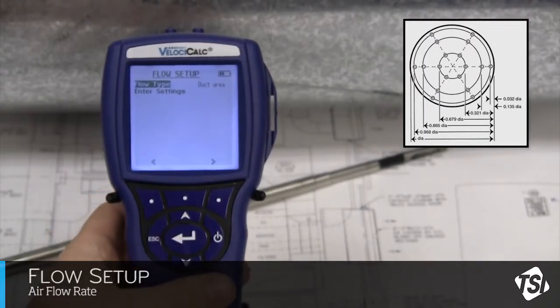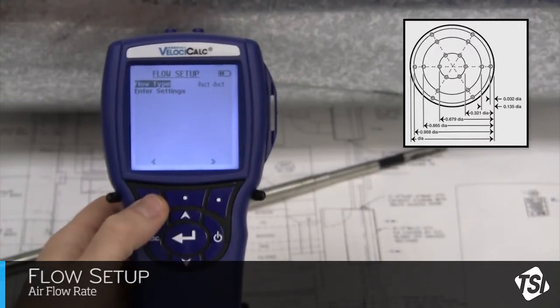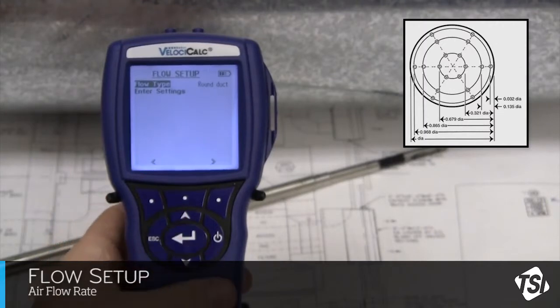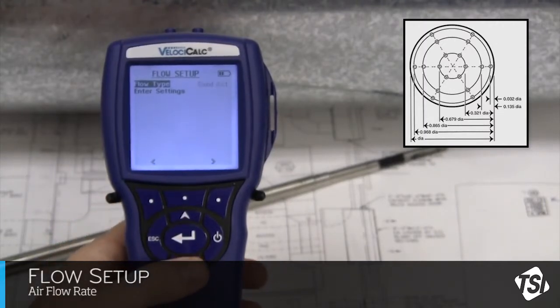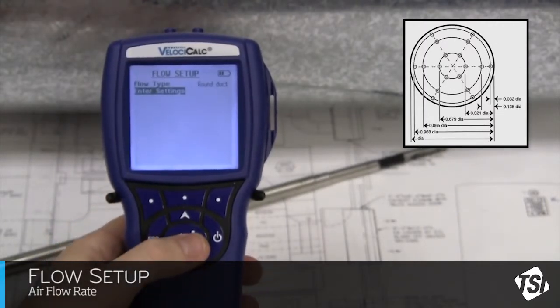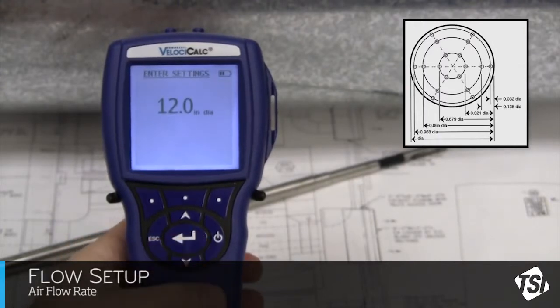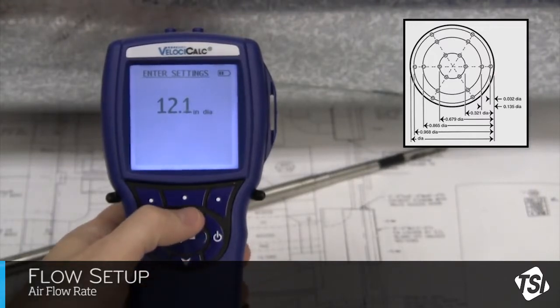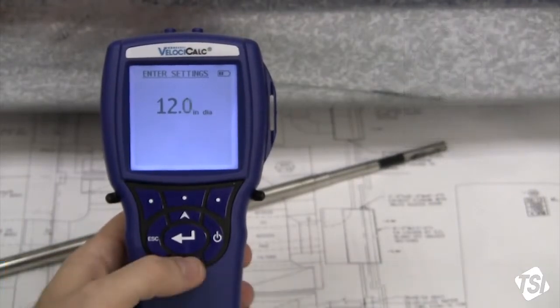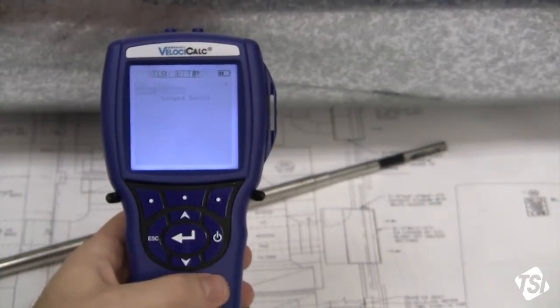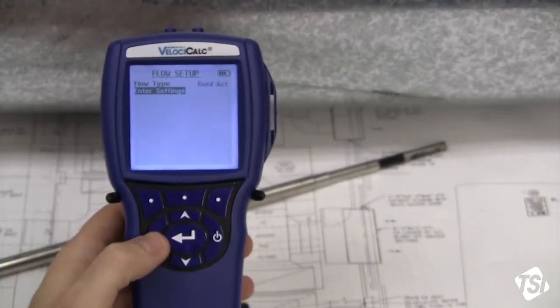For the purpose of this example, let's assume we are measuring in a round duct. So I display that option, arrow down to Enter Settings, and press the Enter button. I will now enter in the dimensions of the duct, in this case the diameter because we are measuring a round duct, using the up and down arrows. I hit Enter to save these changes. Then press Escape to move back to the main menu.